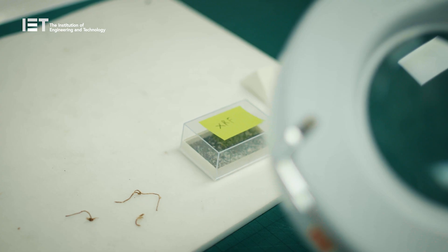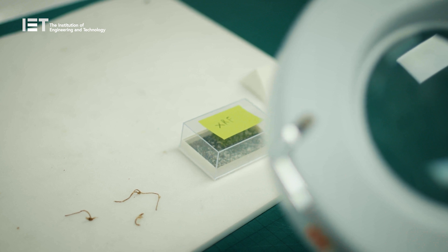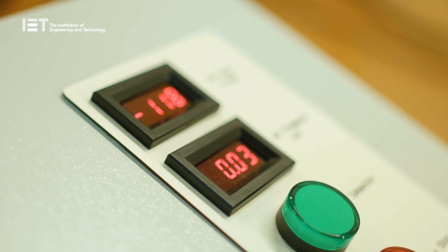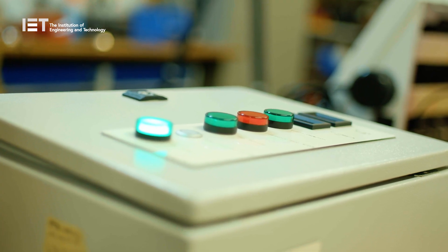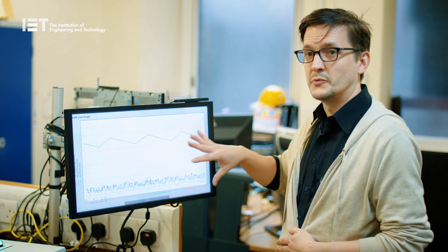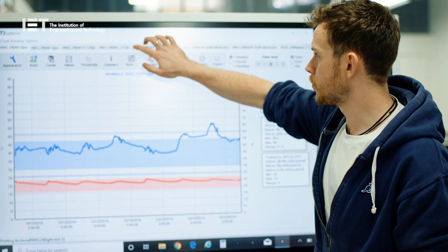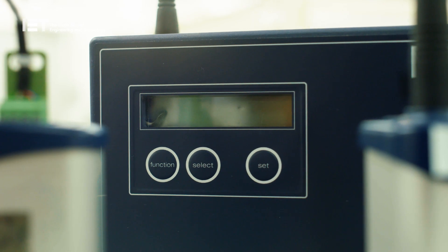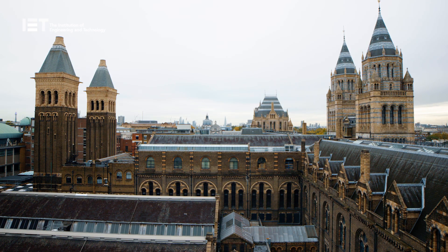How that would be helpful is with regards to things like the BMS data — we can quickly identify if we are having an issue with our environments, and by looking at what the BMS data is also doing, we can hopefully identify what's causing that problem and quickly try to rectify it between our own team and our estates team. The compressors we're using are very large and they tend to create a lot of humidity inside the lines which can cause breakdowns with the pneumatic system. We have to monitor that very closely. This graph also gives us a historical record of when things go wrong and we could use that data to actually predict when other faults may occur and also tell if there's a steady increase in current. So having this data is very useful to all of us.